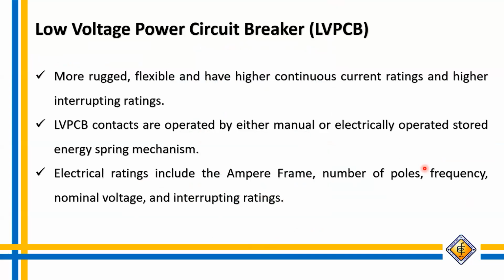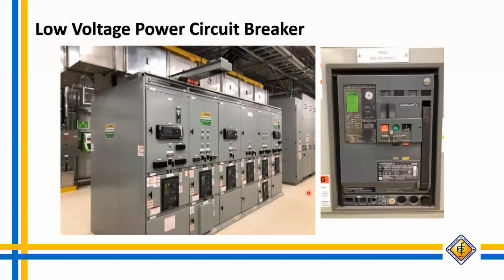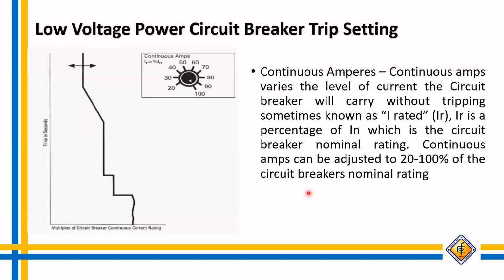Low voltage power circuit breaker. The LV PCB is more rugged, flexible, and has higher continuous current ratings and higher interrupting ratings. And the contacts are operated either manually or electrically. Electrical ratings include the ampere frame, number of poles, frequency, nominal voltage, and interrupting ratings. Sample of a low voltage power circuit breaker. So next one, this is the tripping capabilities or tripping characteristics of the low voltage power circuit breakers.